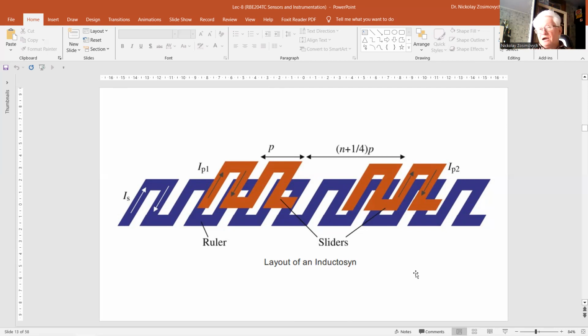Measurement frequencies are around 10 kilohertz. The performance is mainly limited by the readout electronics, in particular the phase measurement accuracy. The accuracy can be better than 0.001 radian. It's approximately 3 minutes of arc, or as we say, arcmin, whereas a resolution down to 40 seconds of arc can be achieved. If you remember, 1 degree is 60 minutes of arc, or 3600 seconds of arc. Okay?